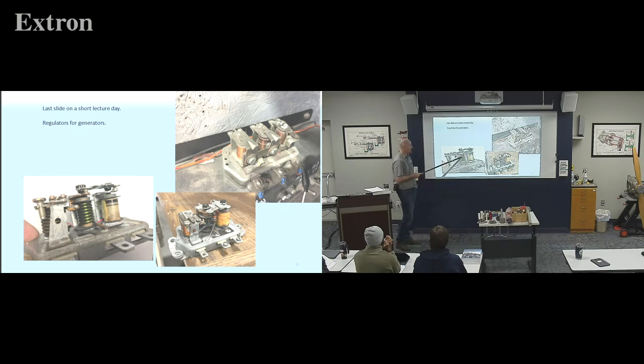And it runs through that wire, and if the amperage gets above what our generator is rated to handle, so if it's a 50 amp generator, I'm going to set the spring on that guy, because I can adjust them. I'm going to set the spring to say, hey, if I get more than 50 amps coming through here, that's too much, we're going to open that little contact for me. So whether the voltage gets too high or the amperage gets too high, we're going to open those contacts. That's why those are connected together.